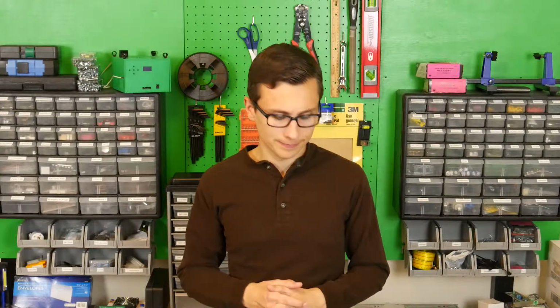As long as we're trying to duplicate that, in case there's a piece of equipment plugged in that relies on that dependency, I'd hate to blow something up or zap someone, or have the case of a piece of electronics tied to neutral, which is actually floating around at like 50 volts AC with respect to ground - it just doesn't sit right with me. So I'm going to make neutral tied to ground the way it was meant to be. That's what the transformer lets us do, while also reducing our DC bus voltage, which will make the conversion from battery voltage to our DC bus easier, and mean we can have a step down PFC from mains. And that's all.